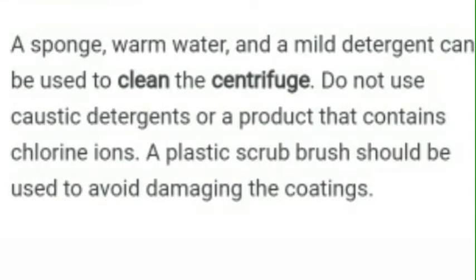And how can it be cleaned? A sponge, warm water and a mild detergent can be used to clean the centrifuge. Do not use caustic detergent or a product that contains chlorine ions. A plastic scrub brush should be used to avoid damaging the coatings.